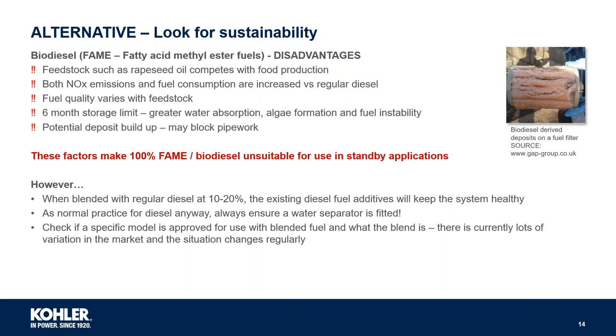So these factors make 100% FAME biodiesel unsuitable for standby applications. However, when blended with regular diesel at around 10 to 20% concentration, the existing fuel additives will keep the system healthy. And as is normal practice for diesels anyway, always ensure a water separator is fitted.